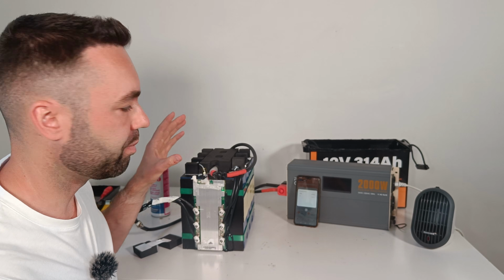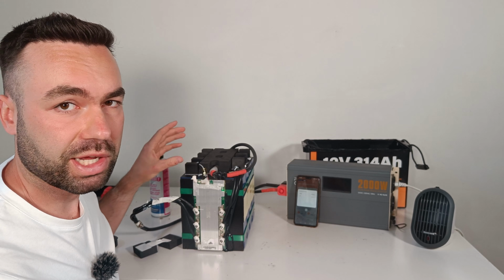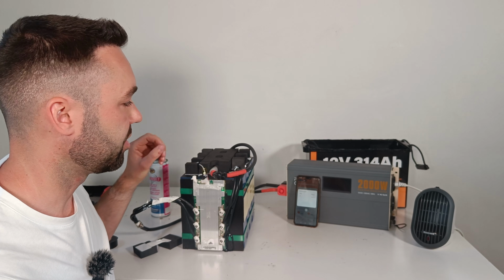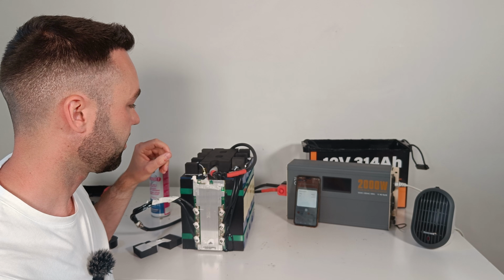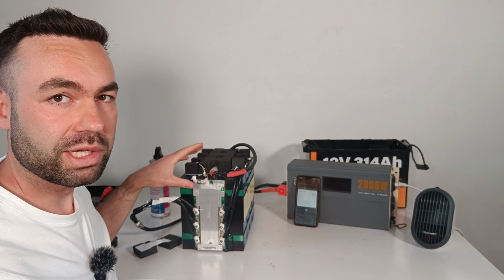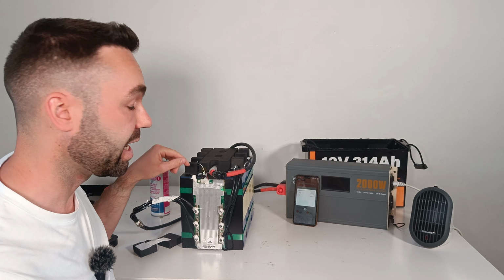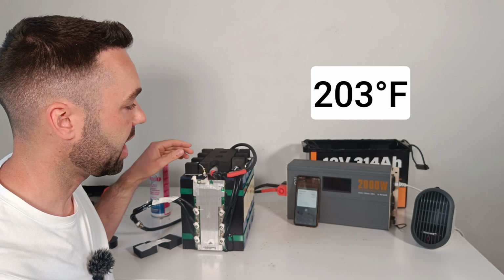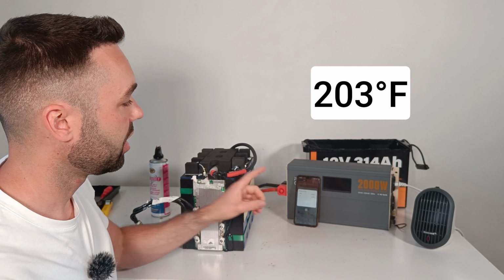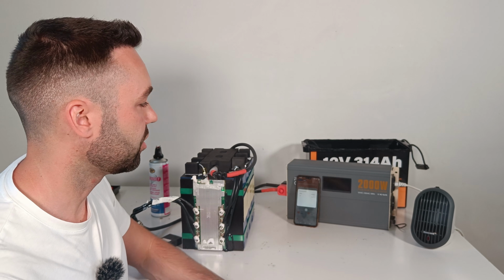That's really bad. I will open up the BMS and see if there's an actual temperature sensor inside or not. Normally the BMS should trigger at 95 degrees Celsius, and that should be the highest temperature, not 120 degrees Celsius.